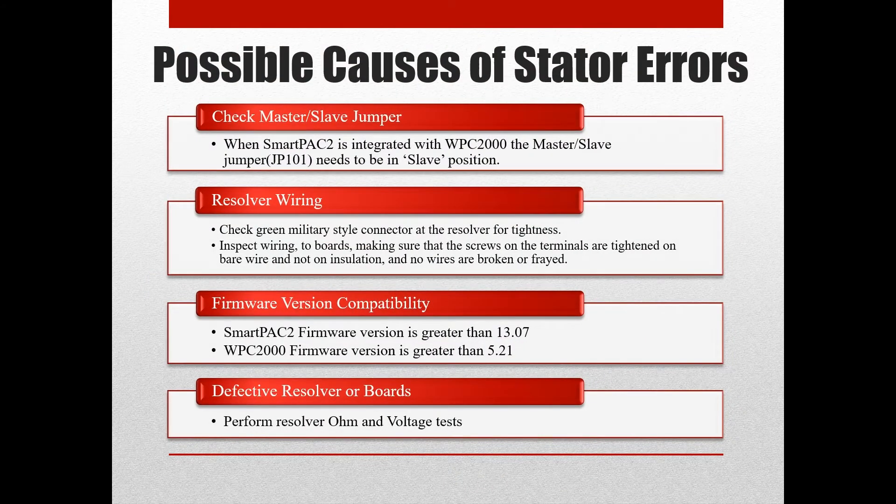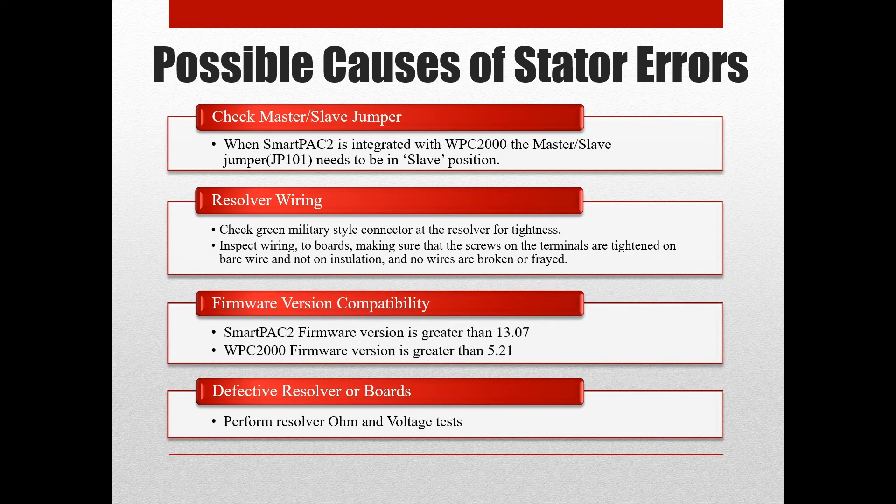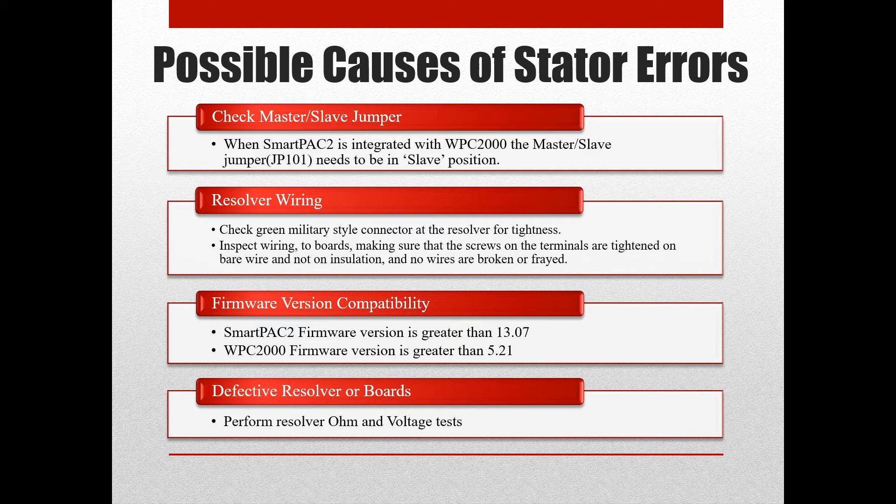Some of the possible causes of resolver stator errors are: the master slave jumper in the wrong position, resolver wiring, firmware compatibility issues of the SmartPAC2 and WPC-2000, and lastly, a defective resolver or boards in the system.